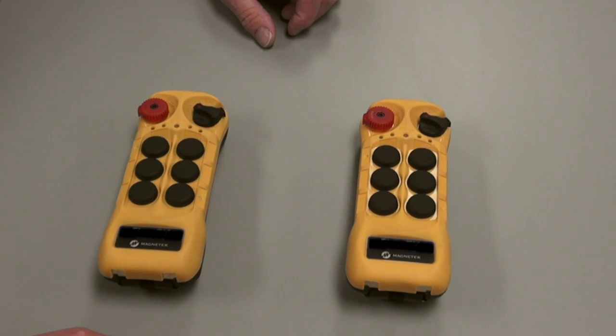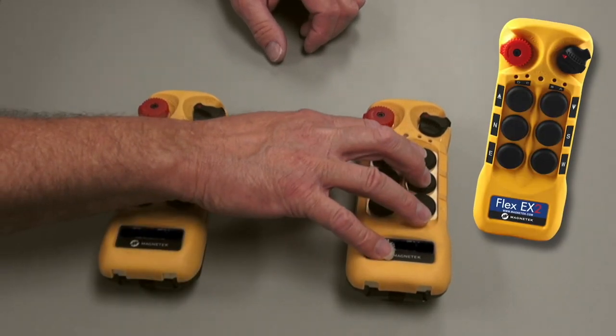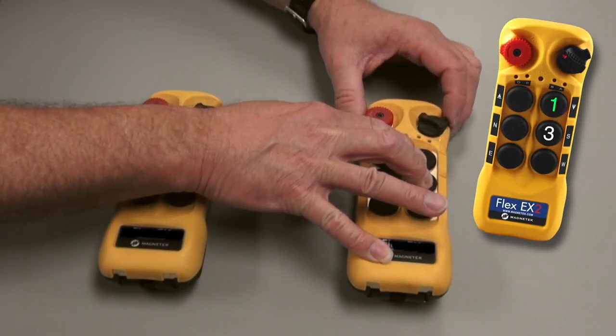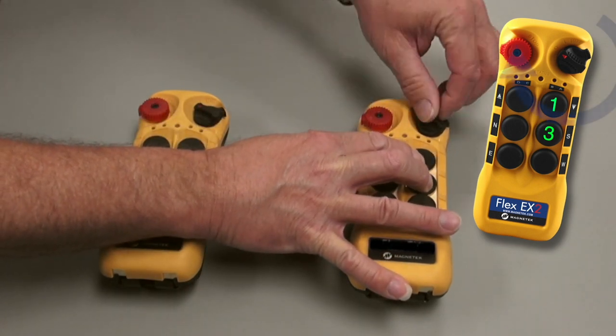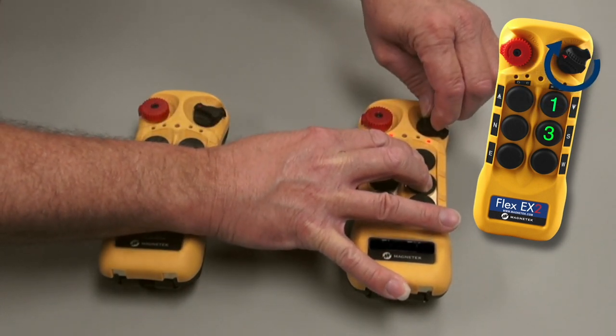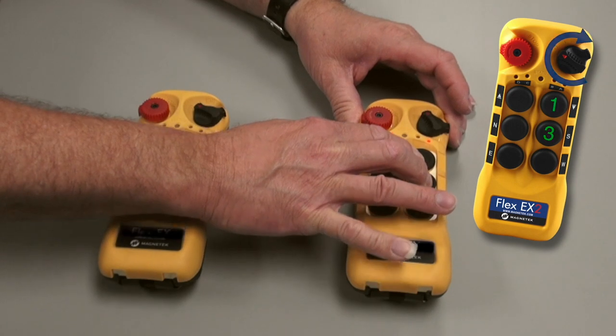We will now enable the transmitter's programming mode. To enable programming mode, we will depress buttons 1 and 3, then turn the key switch to the on position. To exit programming mode, the transmitter must be powered down.